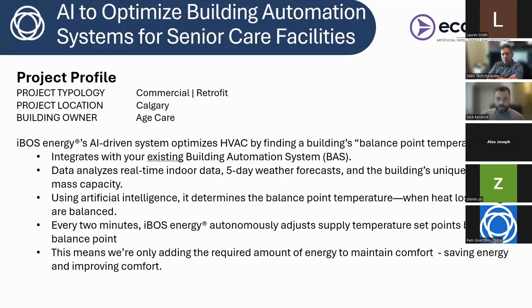The way we do that is we prepare the building ahead of time. So we watch the 5-day weather forecast. We have a sensor on site to read the outside air temperature in real time as well. And we collect those data points from those temperature sensors. Every 2 minutes, the algorithm is recalculating, making sure we're on the right path to keeping everybody comfortable in the building. The next one, please.